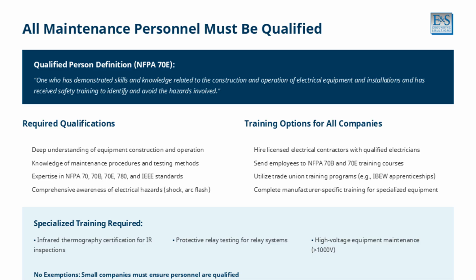Training options exist for all companies, including small businesses. Hire licensed electrical contractors with qualified electricians. Send employees to NFPA 70B and 70E training courses. Utilize trade union training programs such as IBEW apprenticeships or complete manufacturer-specific training for specialized equipment. Specialized training is required for infrared thermography certification, protective relay testing, and high-voltage equipment maintenance above 1,000 volts. There are no exemptions. Small companies must ensure personnel are qualified.